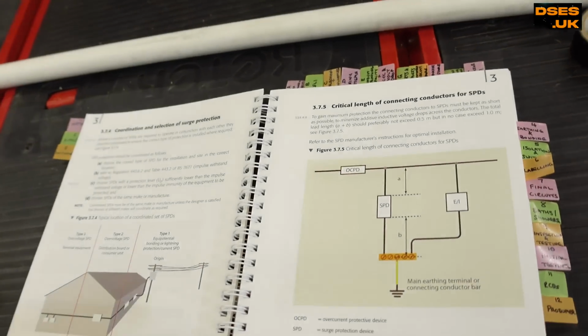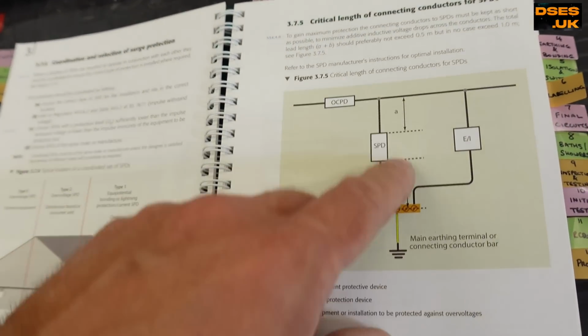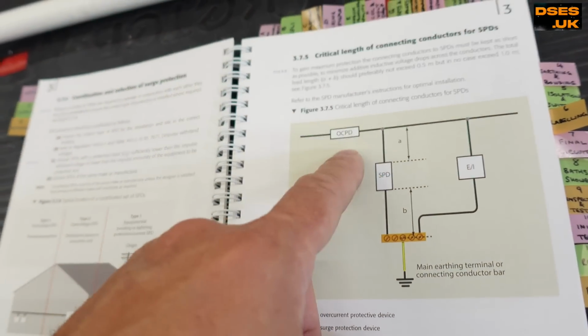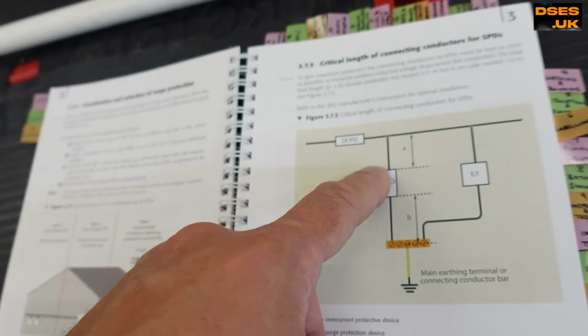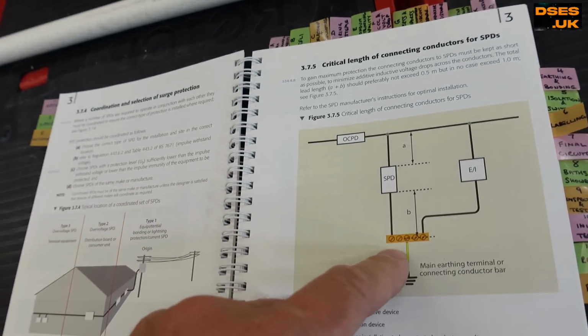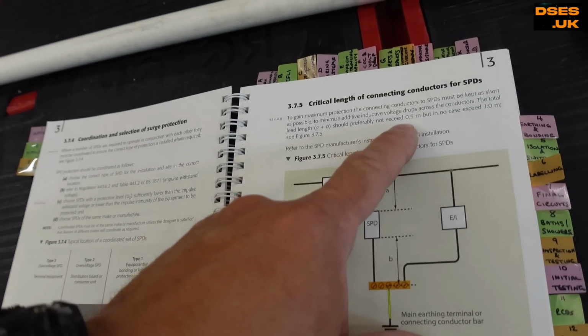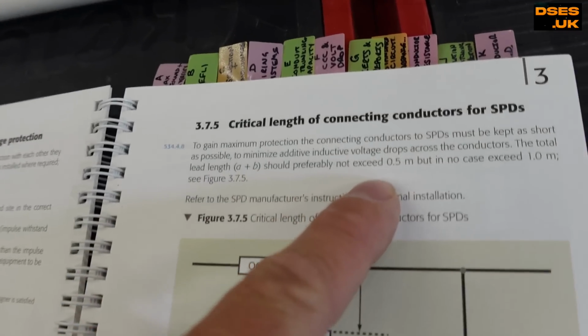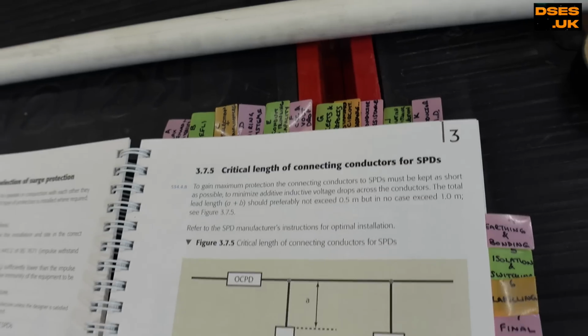What it says here is that the length of A, the wiring from the overcurrent protected device to the SPD, and the wiring of B from the SPD to the earth bar, should preferably not exceed 0.5 meters, but in no case exceed 1 meter.